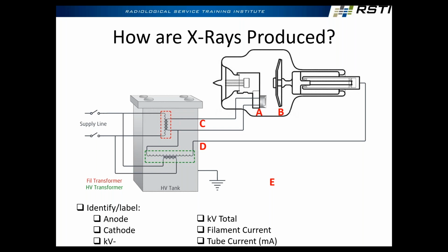3 amps of filament current over here, and you increase the kV. The tube current would go up, because now there's more potential sucking those 3 amps across. But when the doctor says, I want 100 mA, they mean, I want 100 mA. I don't care what the kV is. They want independent control. So when we calibrate these systems, we have to have the ability to change the kV, and there's going to be a different filament current. It might need 3 amps at 80 kV, 2.6 amps at 100 kV, and 2.2 amps at 120 kV. So that's all things that we're going to calibrate when we do our filament calibrations to ensure accuracy of the mA. We don't care what the filament current is. The customer doesn't care what the filament current is, but they do care about the tube current because that gives you the density that you want on the image.